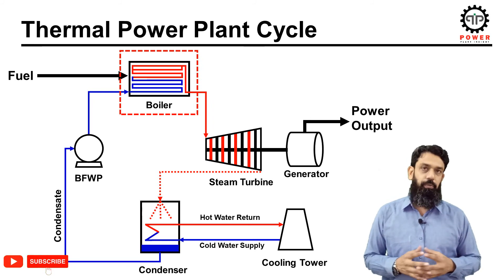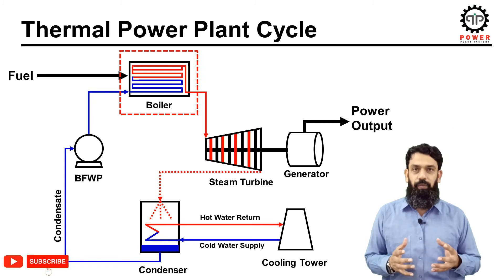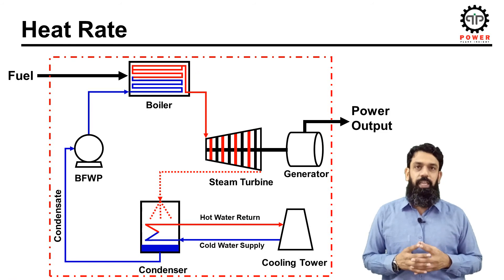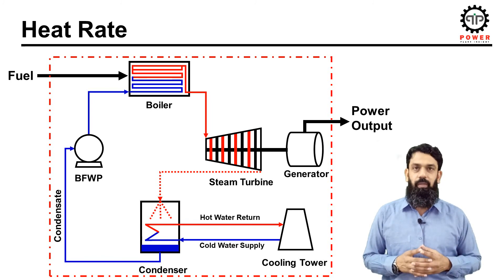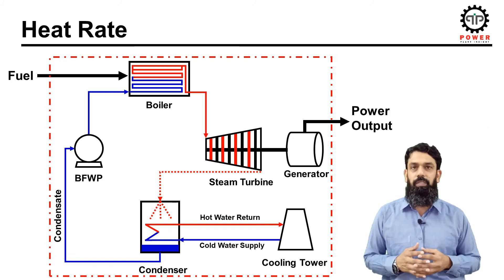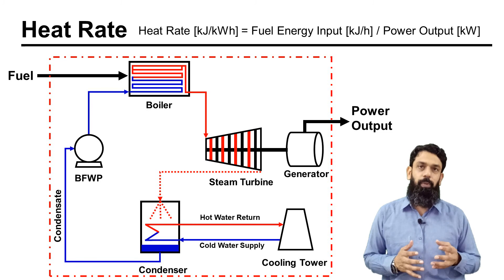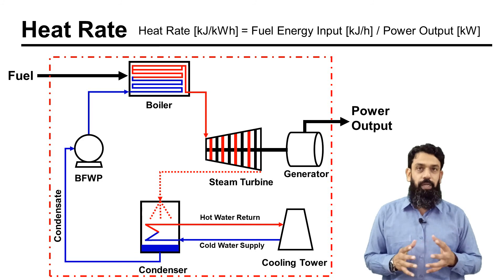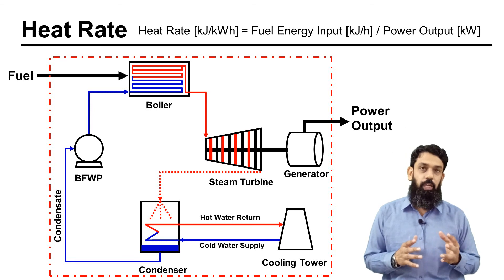During discussion of a thermal power plant, heat rate is a commonly used term. To understand heat rate, we draw an imaginary boundary around the thermal cycle — fuel is used as input and power is obtained as output. Heat rate is the ratio of input to output, or in simple words, the ratio of fuel energy input to power output. Heat rate shows how efficiently a plant converts the heat energy of fuel into electrical energy — meaning kilojoules of energy consumed to generate per kilowatt-hour of electricity.